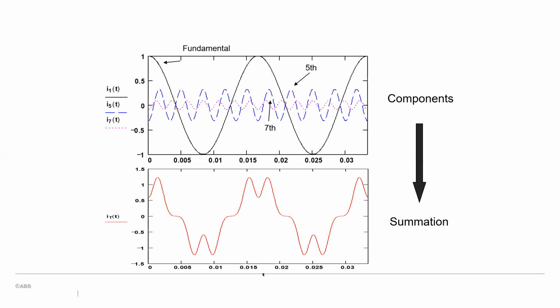This is harmonics. Normally, if you see this black waveform, this is the fundamental current. Normally, the harmful harmonics are the odd harmonics. The even harmonics cancel out each other. The odd harmonics add up and cause disturbance. If you see this blue waveform, this is the fifth harmonic. Then the pink one is the seventh harmonic.